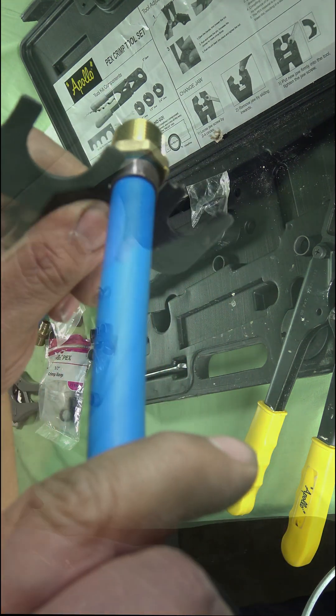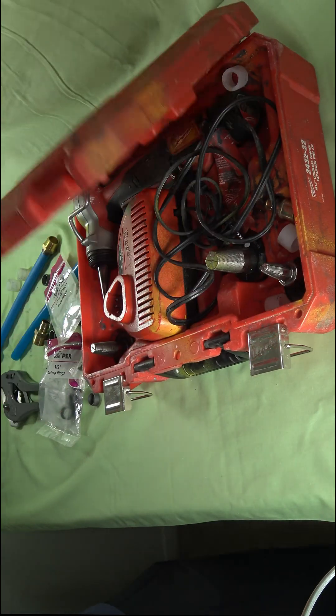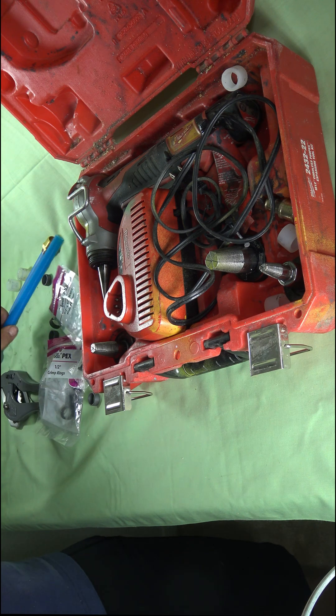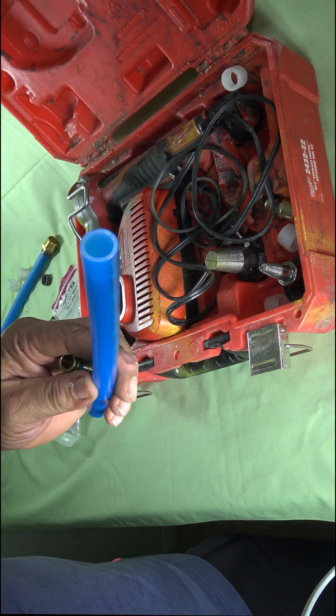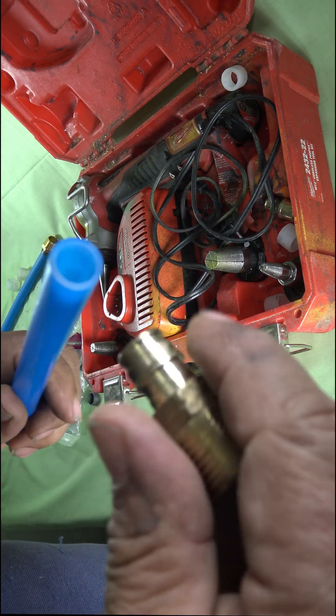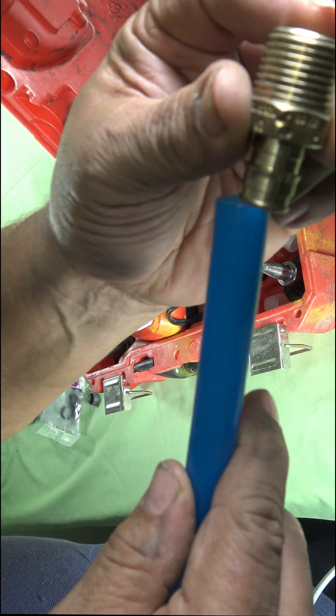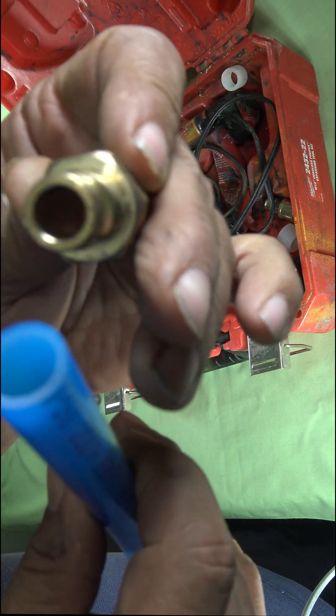It would make it difficult for this gauge to get around the half inch pipe. Now comparing the two — I brought up the Uponor tool and we'll see the difference in the connection. This is the Uponor PEX pipe, which has that little frosted white ring in the middle — that's how you can tell the difference between the two. You'll notice that the Uponor fitting doesn't go in exactly inside that pipe.